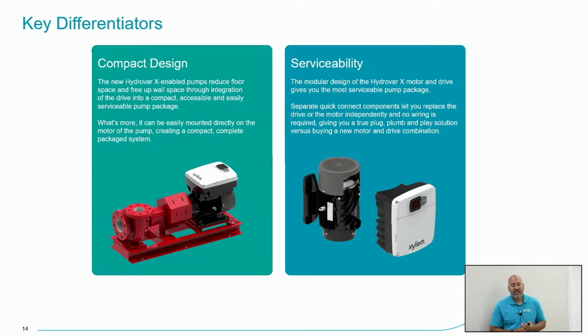A lot of products on the market with these integrated solutions, if a VFD or motor were to go wrong, you have to replace the complete unit. That is not the case with our solution. We can separate the motor from the VFD, so if one or the other goes bad, we can simply swap out the component that is having the issue.